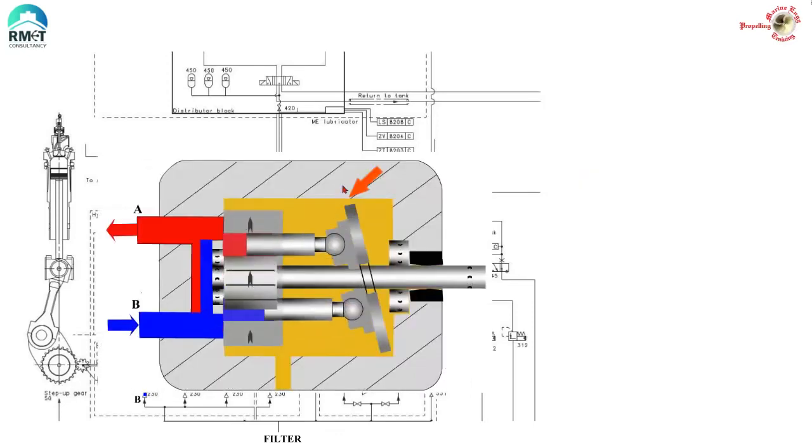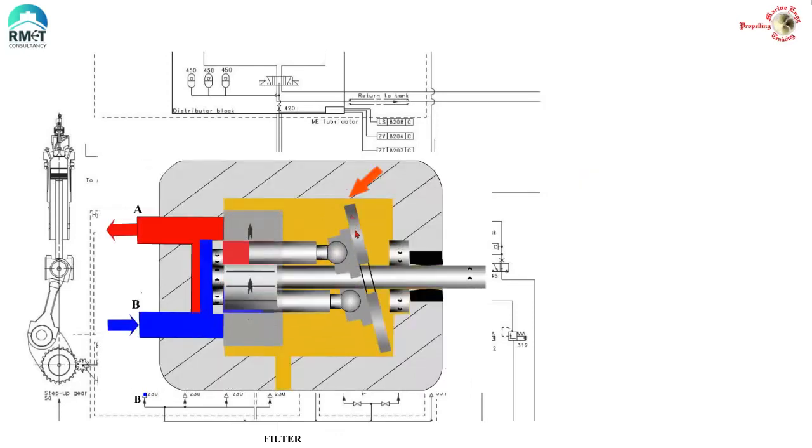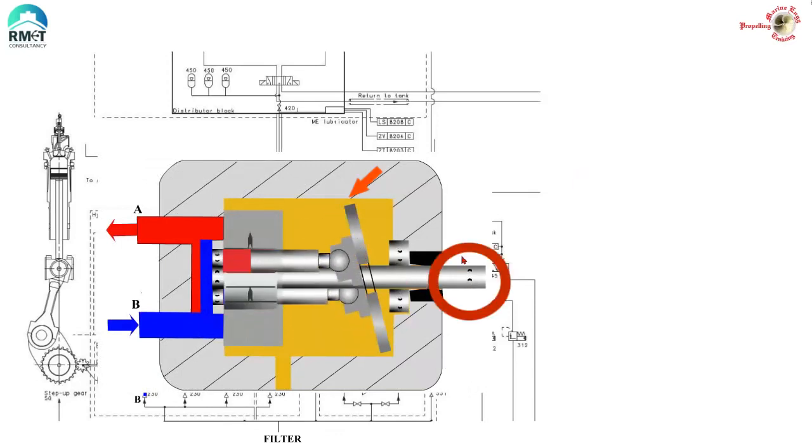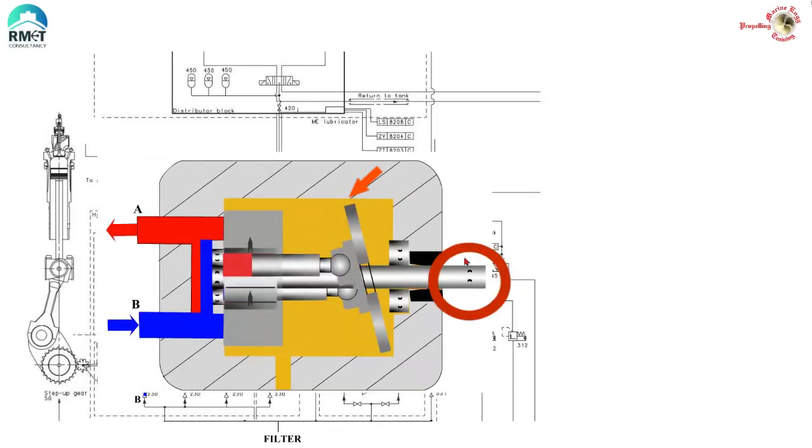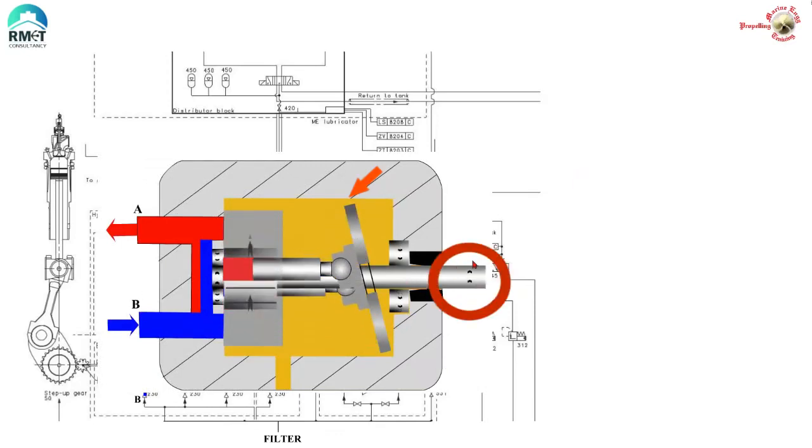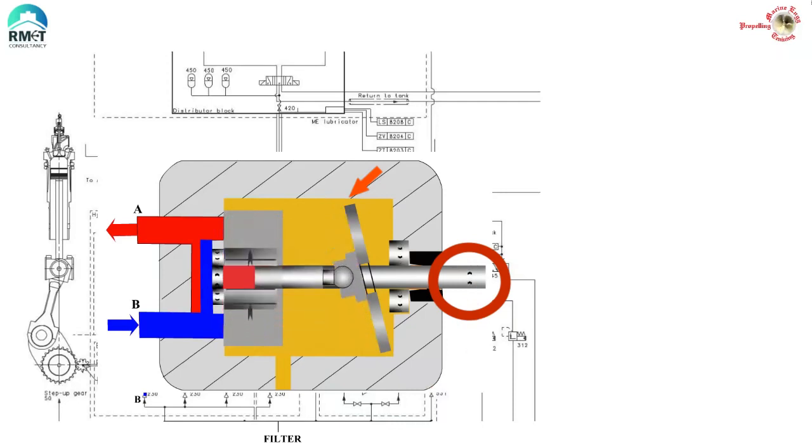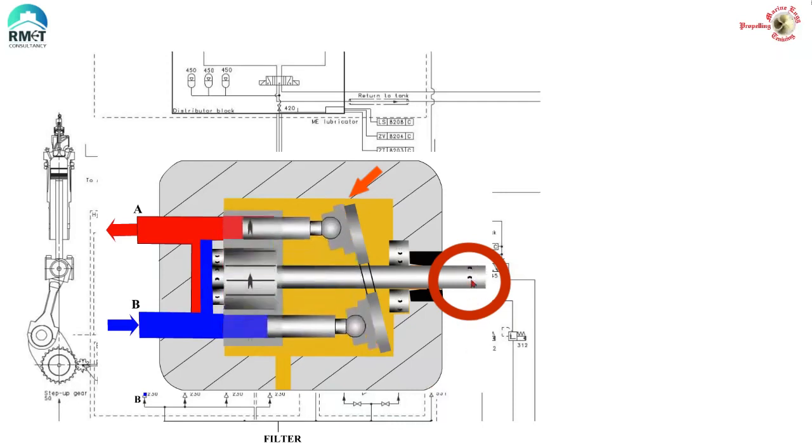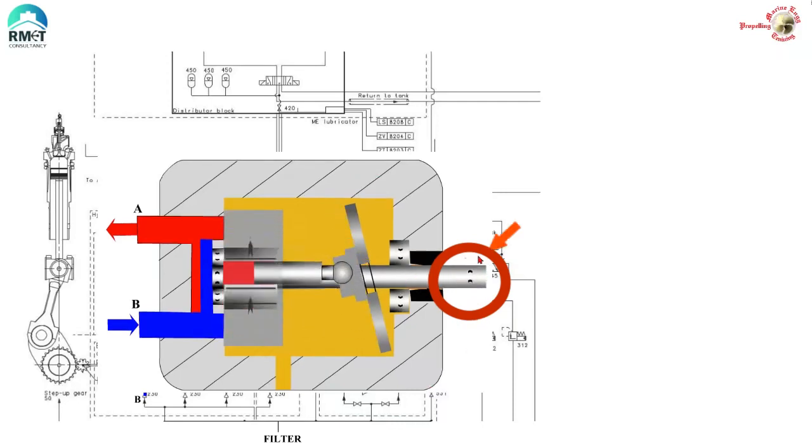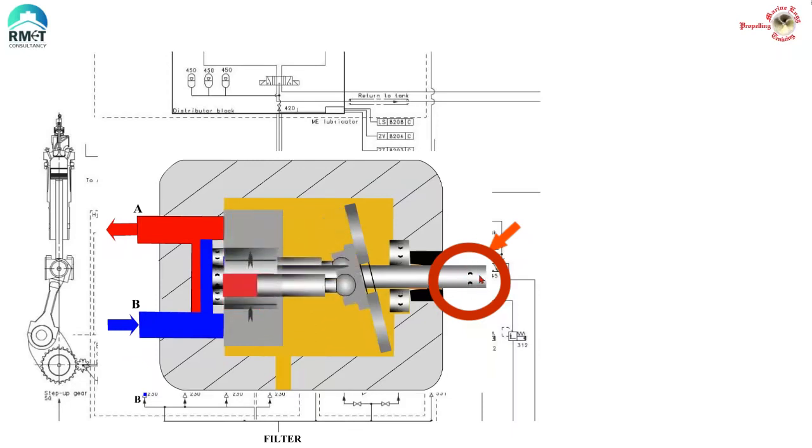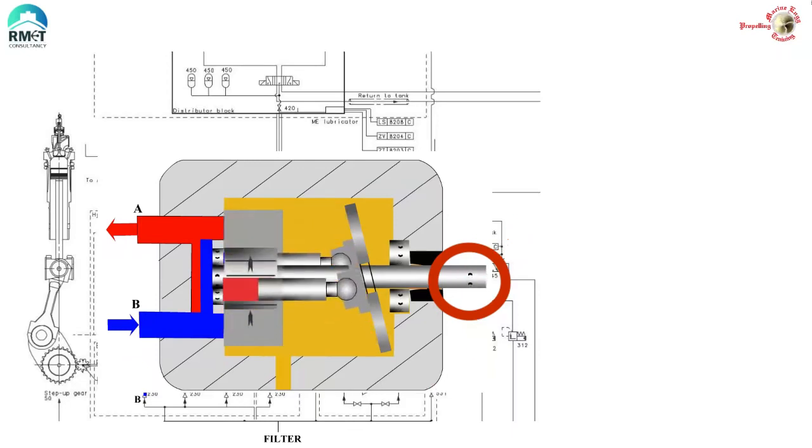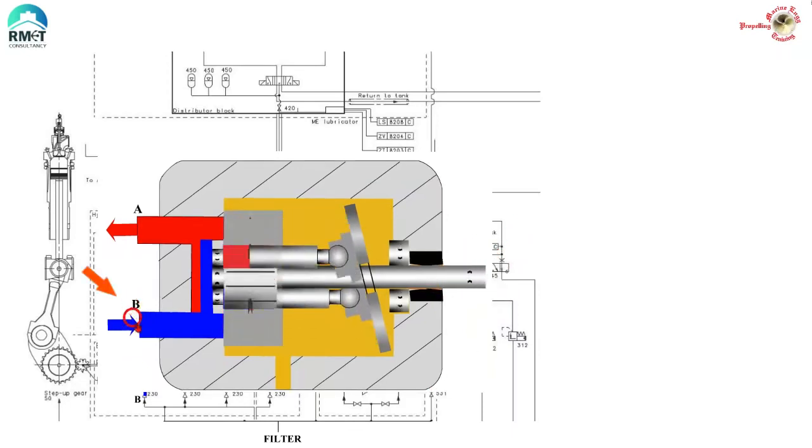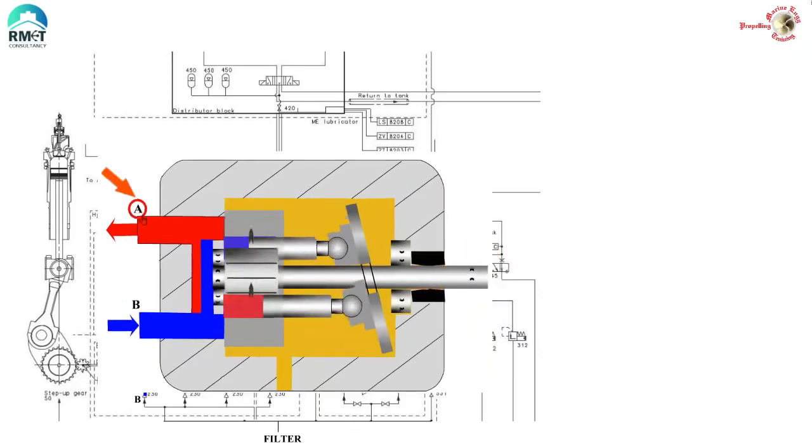Let us start with principle 1 for a variable delivery pump. Here you can see that with the swash plate swinging to the left and with the prime mover rotating the pump shaft in the clockwise direction, the pump is taking suction from the B side and discharging to the A side.